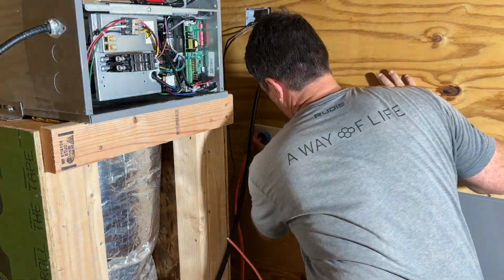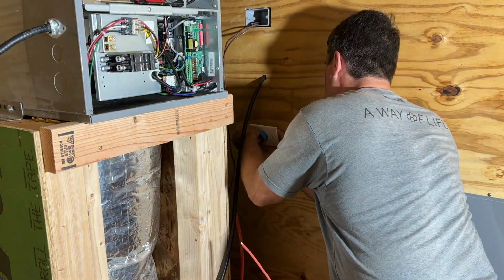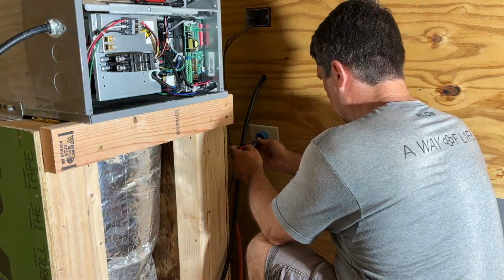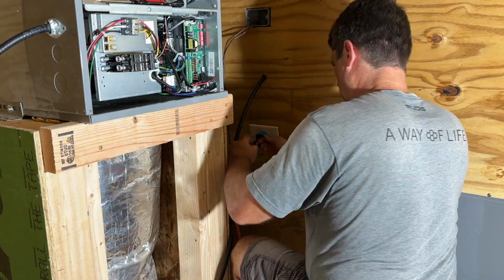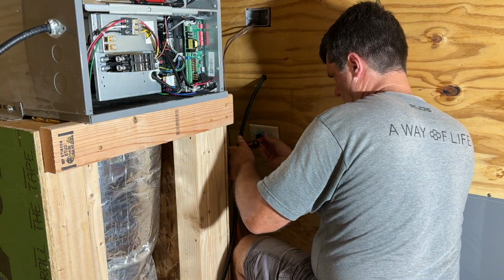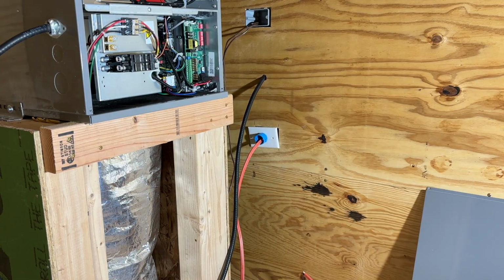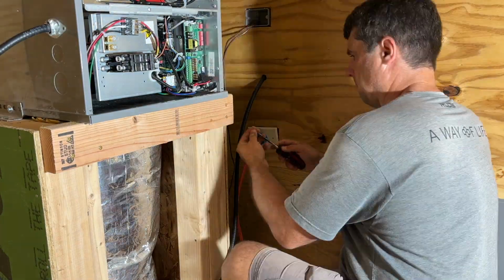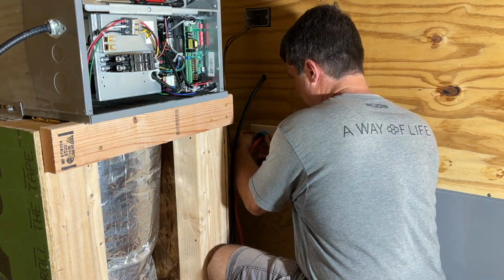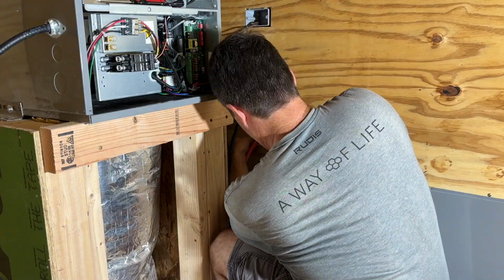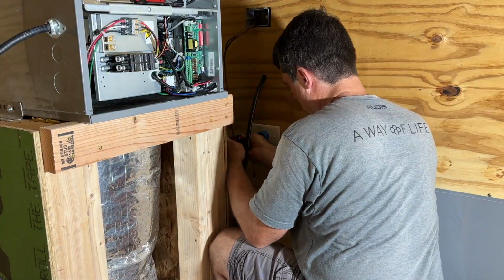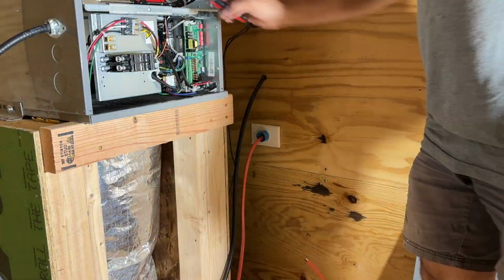Now that we got the power run to the blower and the circuit board there, we can run the power for the auxiliary heat strip. And this comes from the main breaker panel. It is a 30 amp 240 volt circuit, and we're running this in 10-2 Romex. And you're going to see here in a minute, probably going to make people squirm a little bit. I put it in conduit.